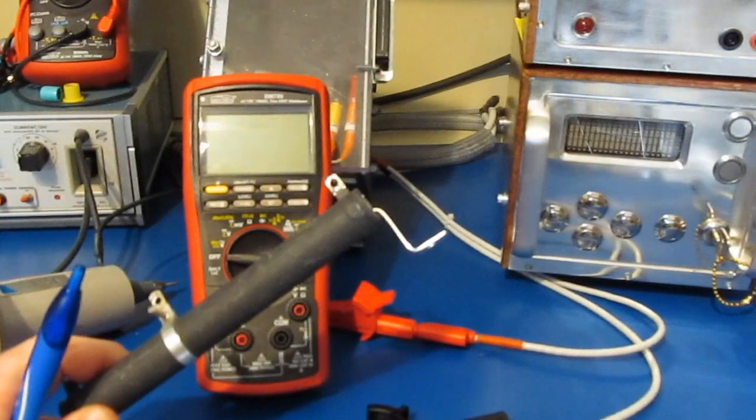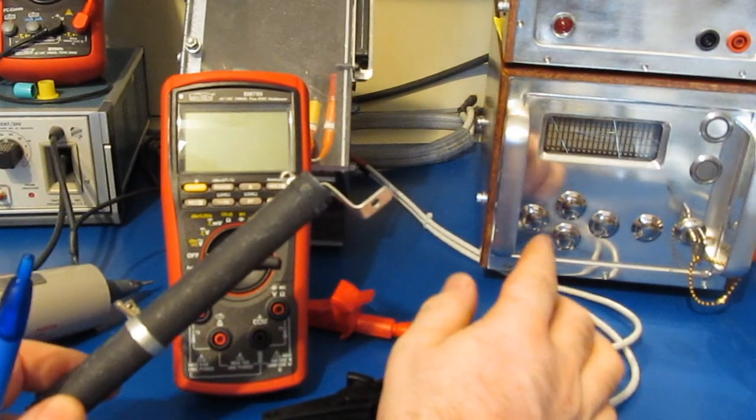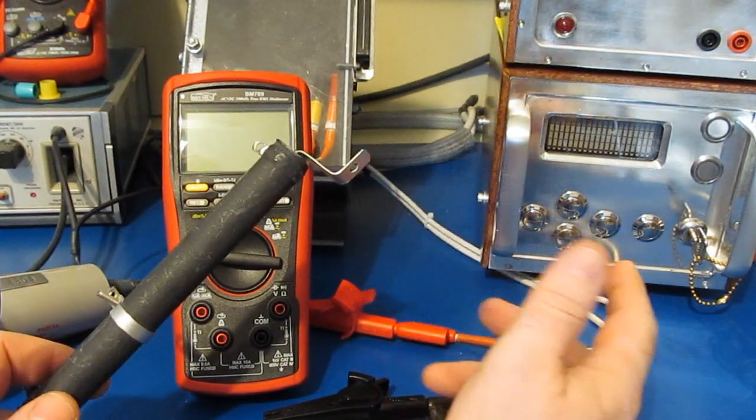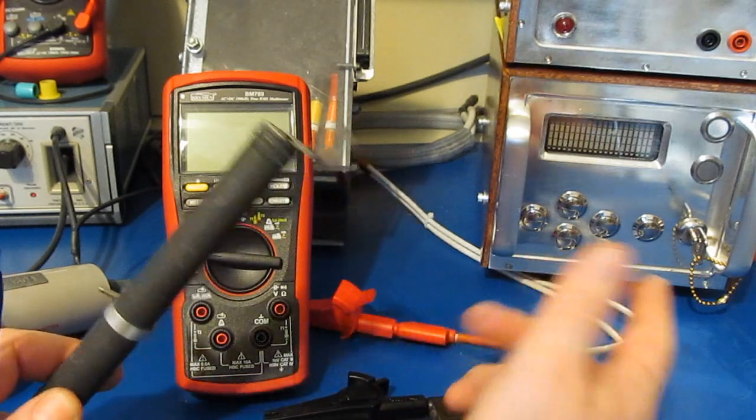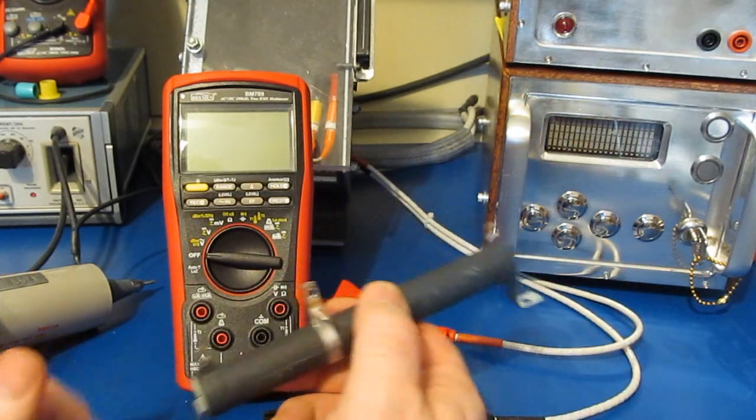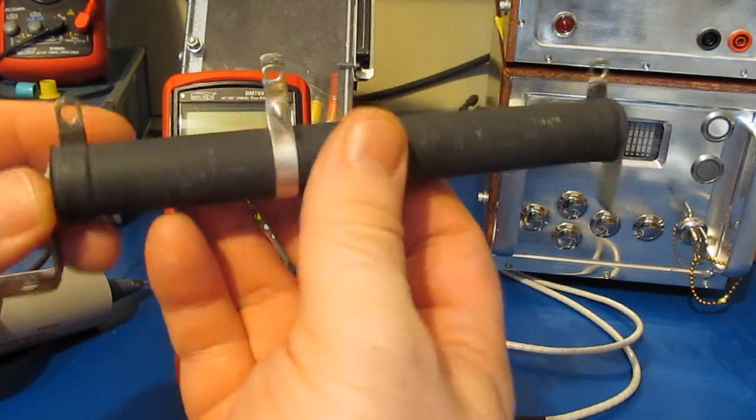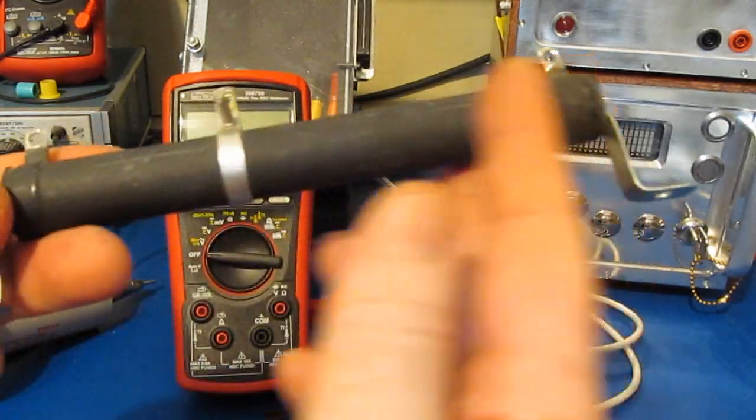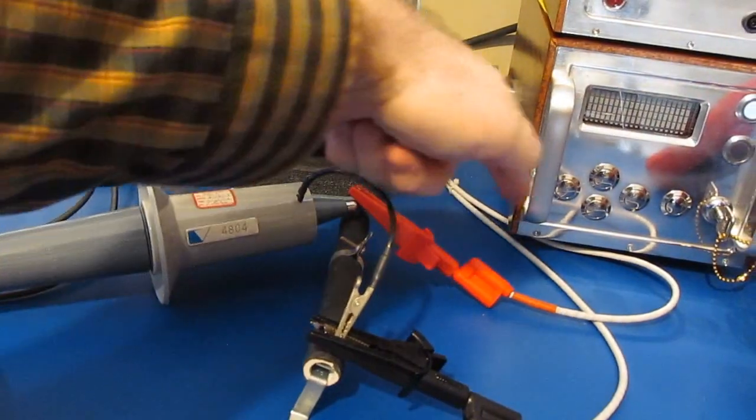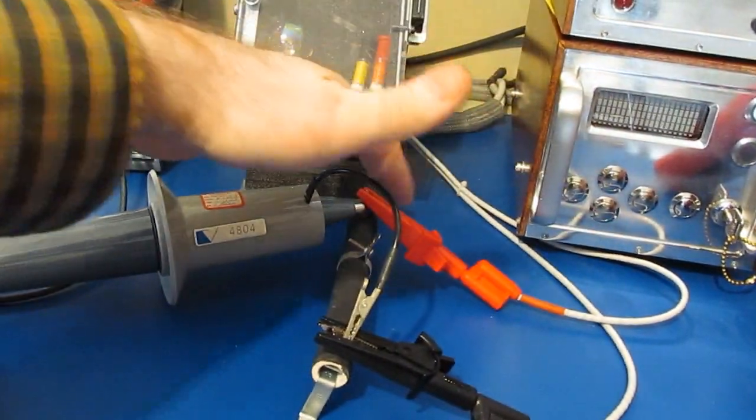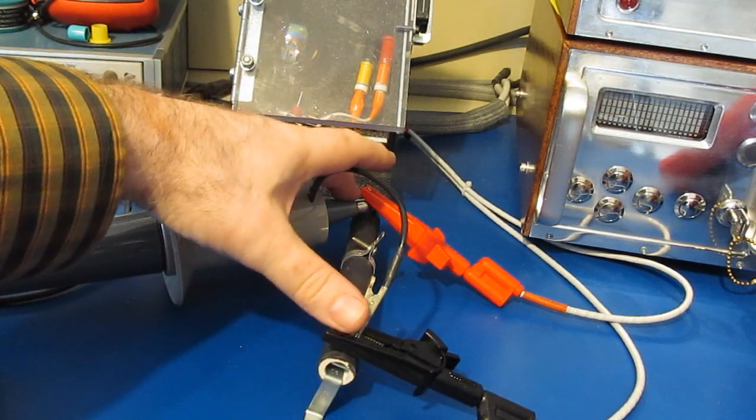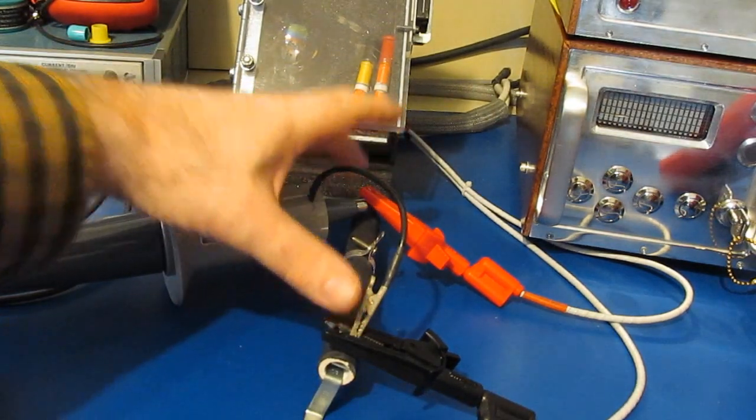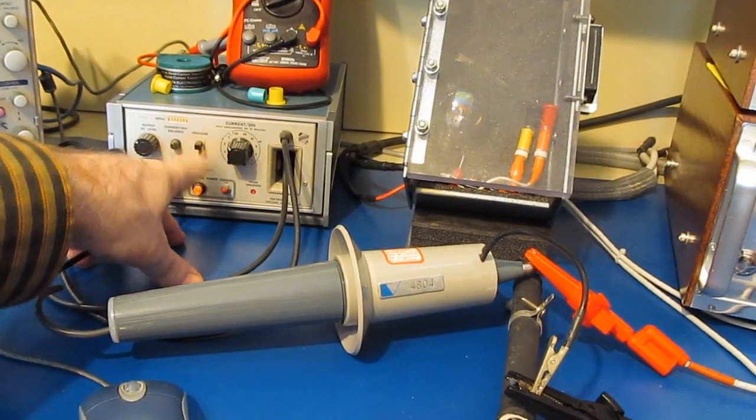I've mentioned that this transient generator has a 2-ohm source impedance. So, for example, at 1,000 volts peak, that's limited to 500 amps or 1,000 divided by 2. What I have here is a 5k ohm resistor. We're going to use this as a starting point to look at the current. Here's the output of the transient generator, attached directly across the resistor. And our oscilloscope probe is attached directly across the resistor as well.